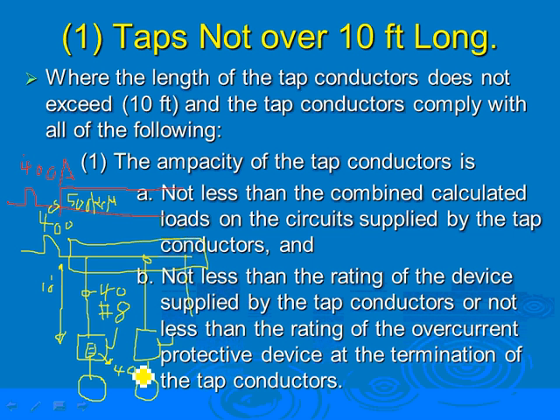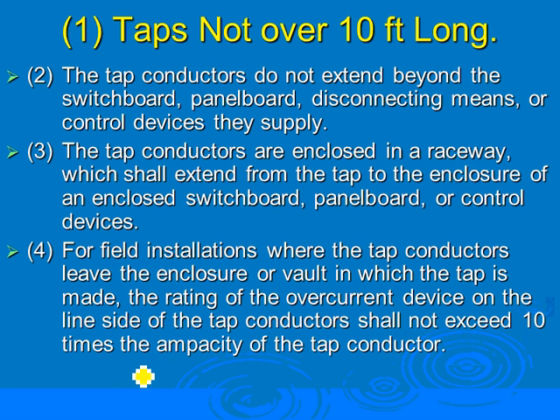Any comments, guys, about this tap rule, that 10-foot tap rule? Do you take advantage of it? Yes, no? You wouldn't put 10 feet on there, but typically it's a 10-foot. Yeah, and this is, I'm going outside. A lot of times, guys, you stay inside the same enclosure. You stay inside the same enclosure. I put the 1/10 here because I'm moving outside the enclosure. Okay, so that's basically what this rule is, and the field installation.